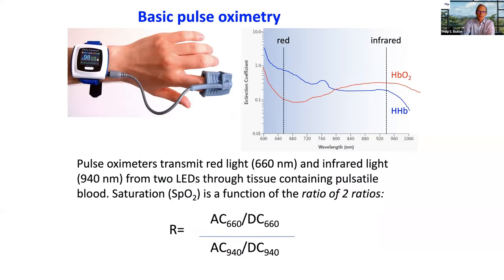Okay, so pulse oximeters have two wavelengths of light, a red and an infrared light signal, and they work on the basis of measuring the pulsatile component of the red light signal versus the static component of the red light signal, divided by the same for infrared light. So it creates a dimensionless number called the R, or the ratio, which is the AC at red light divided by the DC of red light, divided by the same for the infrared wavelength. And that produces a value that is linearly related to saturation and can be calibrated.